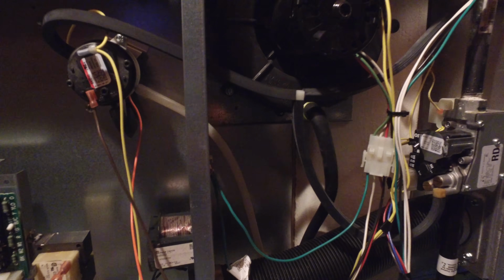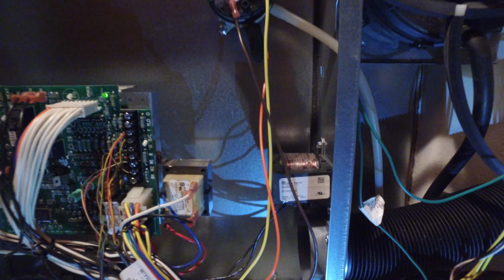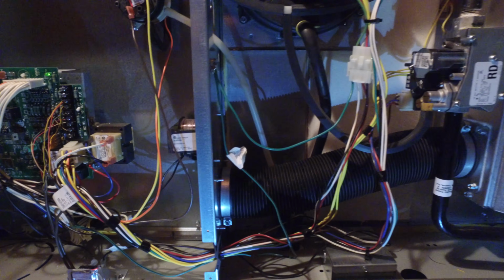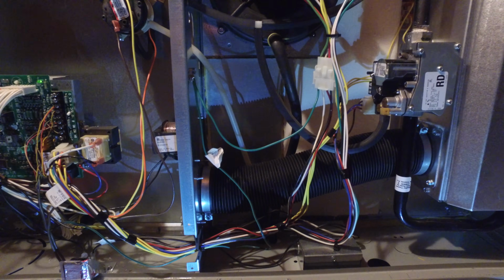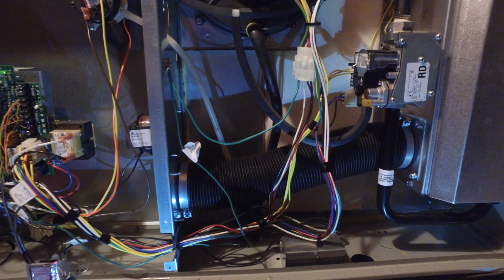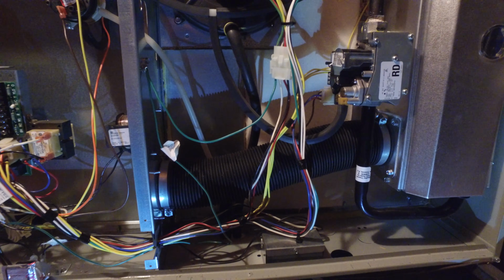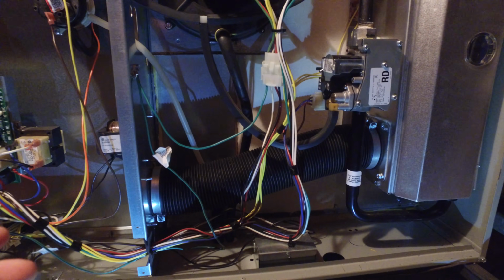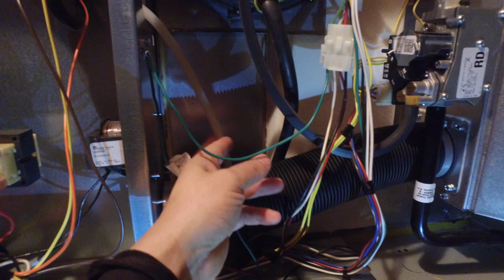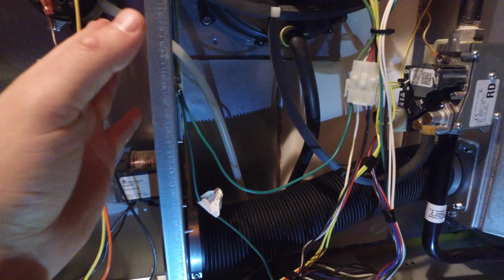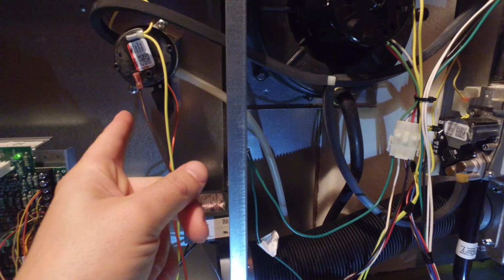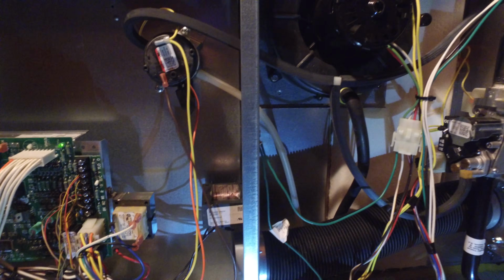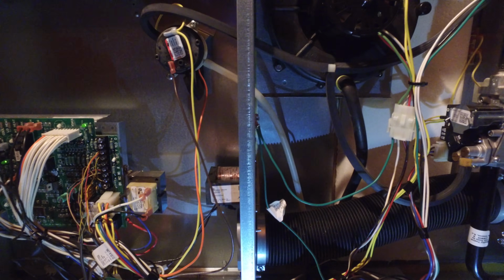It took us a few times to remove this hose and dump the water out, plug it back in, turn the board back on, turn the furnace back on, and let it run. It took like 2 or 3 or 4 times until we realized what was happening was the water kept picking up, and when the water blocks this vacuum line, it doesn't allow this switch to close, which is part of stage 2 on this unit. So that ended up kicking out the error code, and the unit stopped working.